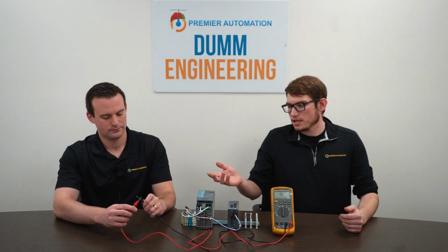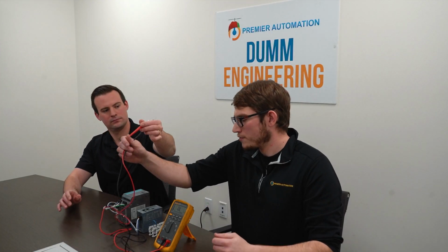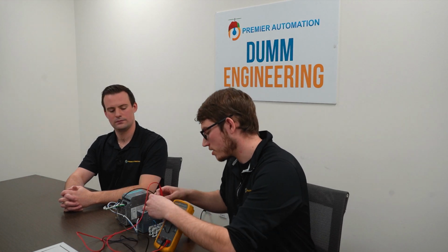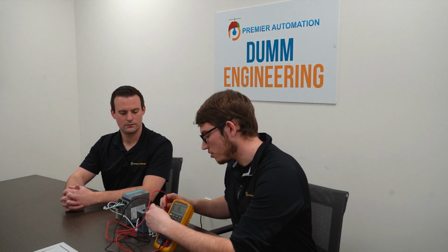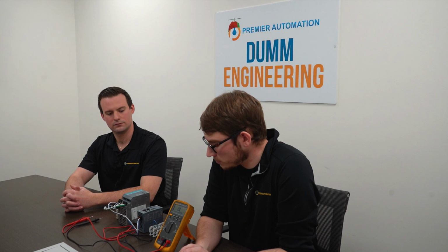Whenever you're testing an electrical system, after you wire something, you want to make sure that it's right so you don't accidentally damage the system if there's an issue. For continuity, you check if there's a low resistance between 2 points. So these two terminal blocks that are wired together will ring because they're connected, but this third one that's completely separate from the other two will not ring. That's part of our standard testing procedure here at Premier, and every wire that we install gets tested as such.